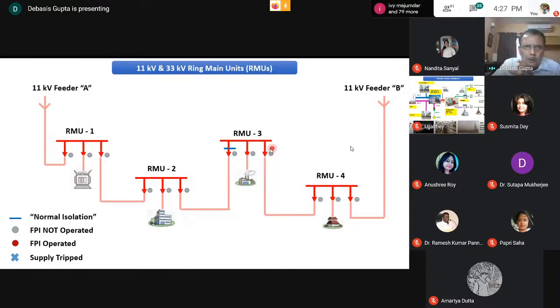Consider 4 RMUs, RMU 1, 2, 3 and 4. Suppose the left hand RMU is fed from a feeder coming from station A, or from one station on two sides of one section. So you have feeder A feeding this RMU, and this leg feeding a distribution transformer. This leg goes to the next RMU, this leg feeds maybe a mall, and this leg feeds another RMU. The blue line means we have intentionally cut it there, isolated, because you can't have two feeders connected continuously - it will act like a bus section. You have to disconnect somewhere, so we have disconnected it here.